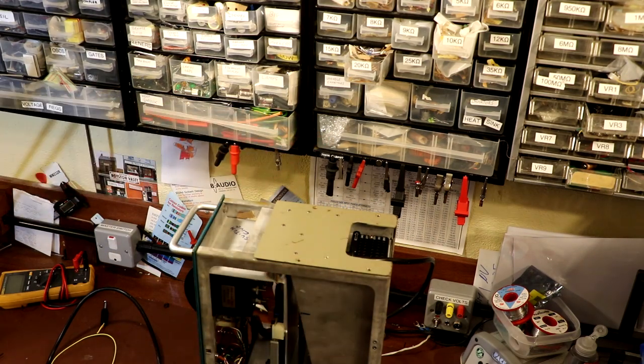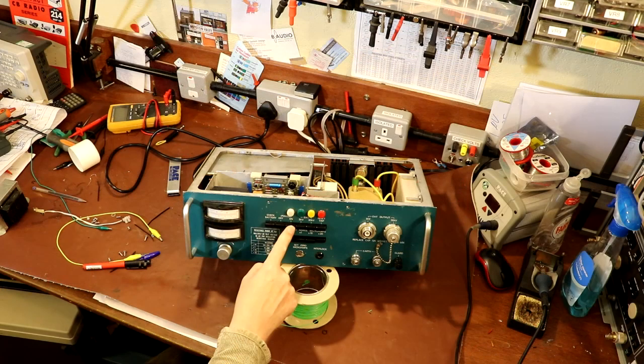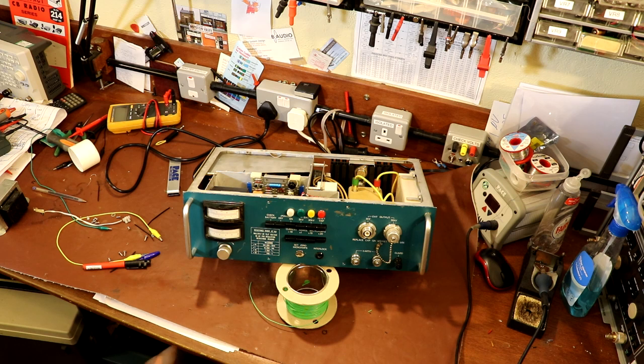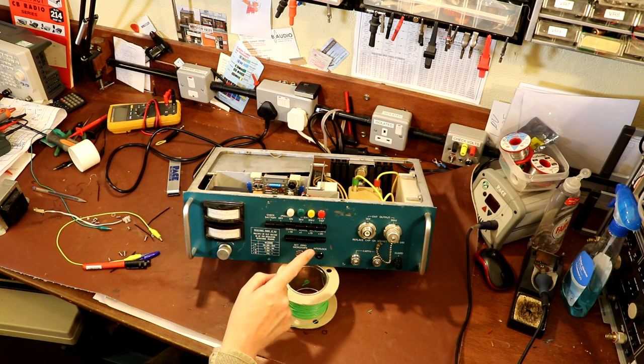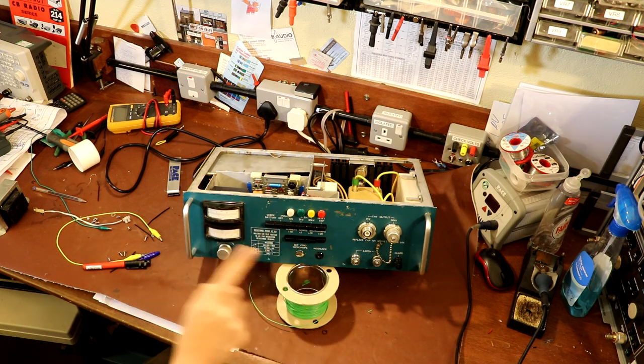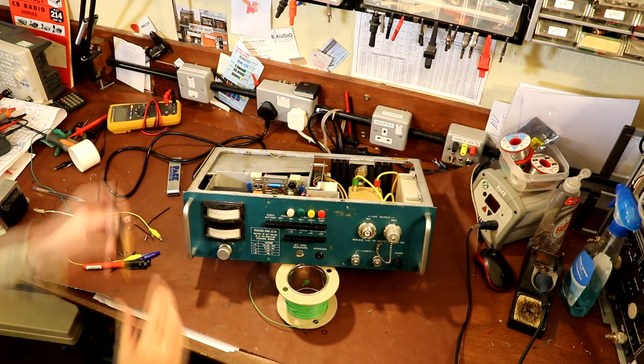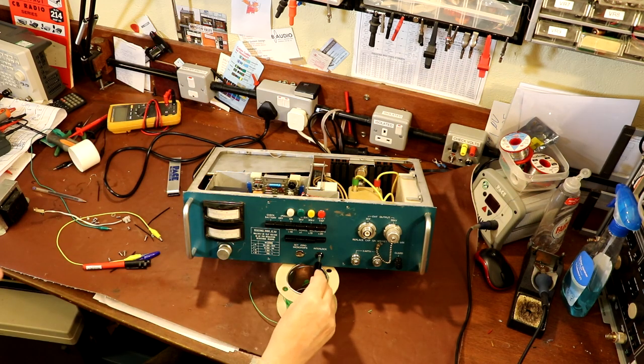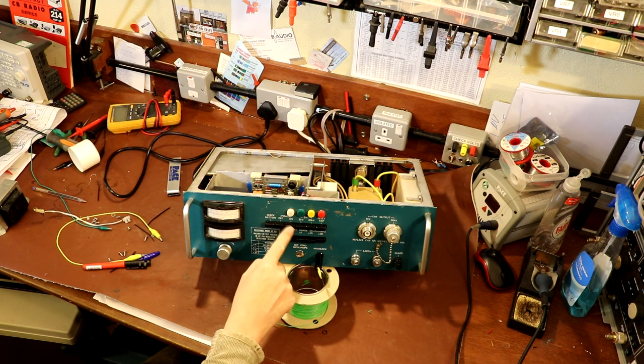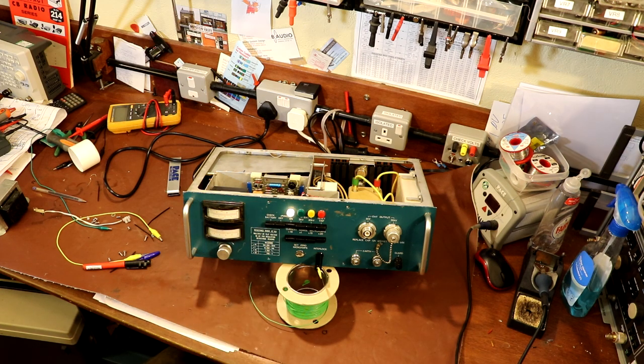Okay, that's lined up. It's just a bit tricky to line those mating connectors up when it comes together. Is it going to come on or is it going to trip out the mains again? 1, 2, 3. Oh. Well, it didn't trip the mains out, but then again, nothing happened either. But I think I know why. Let's have another go. I think we need this interlock plug installed. 1, 2, 3. Oh, and we have some action.